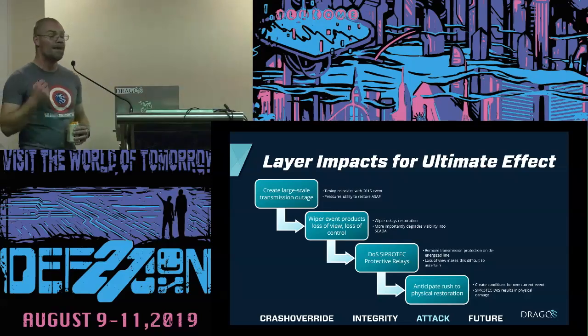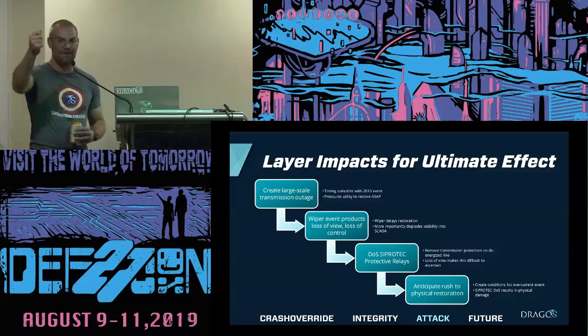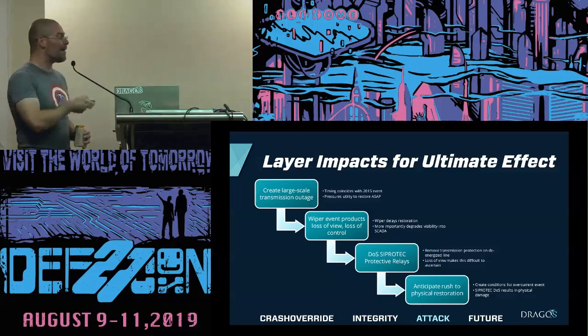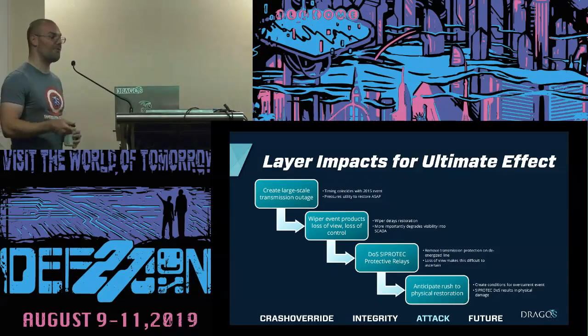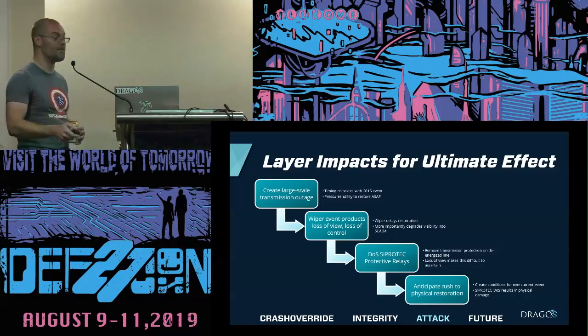Because in that rush to restore operations at the transmission site by flipping those switches in the breaker yard, now you create the conditions for potentially hazardous effects on an unprotected line that you're re-energizing.